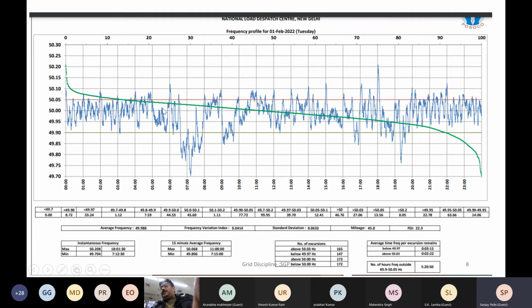The attempt is to keep the frequency within this band. And this daily report from the National Load Dispatch Center also gives the number of hours the frequency was outside this band. You can see for 5 hours it has been outside this band. So basically, this is how it is to be seen. One thing is clear to me, that this is instantaneous.